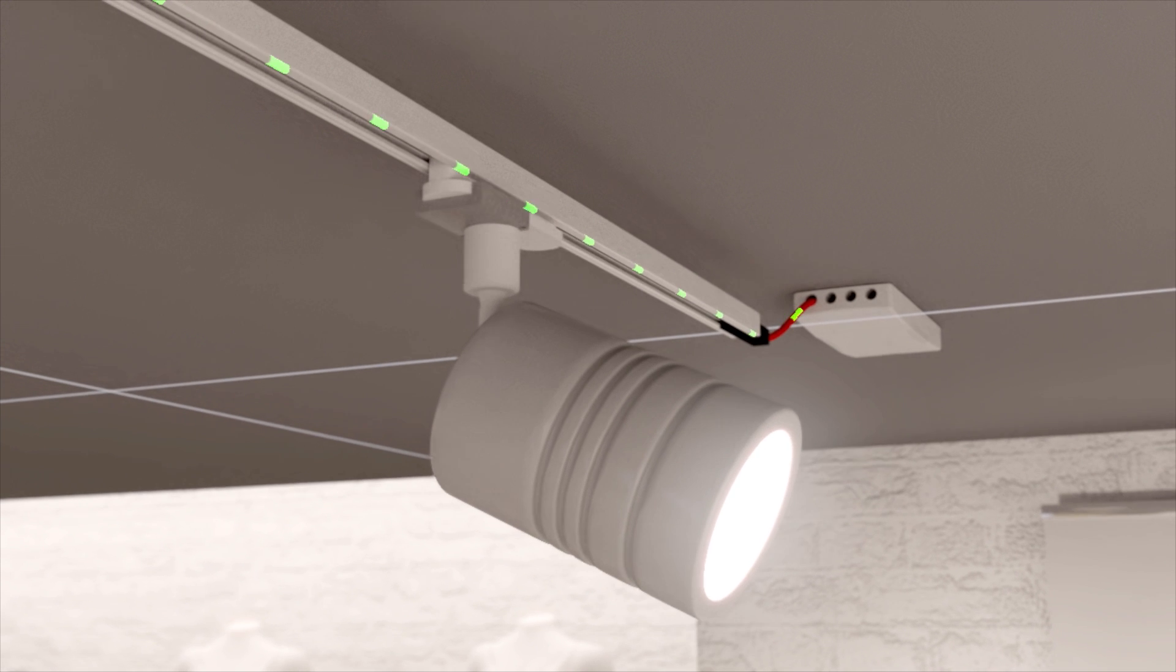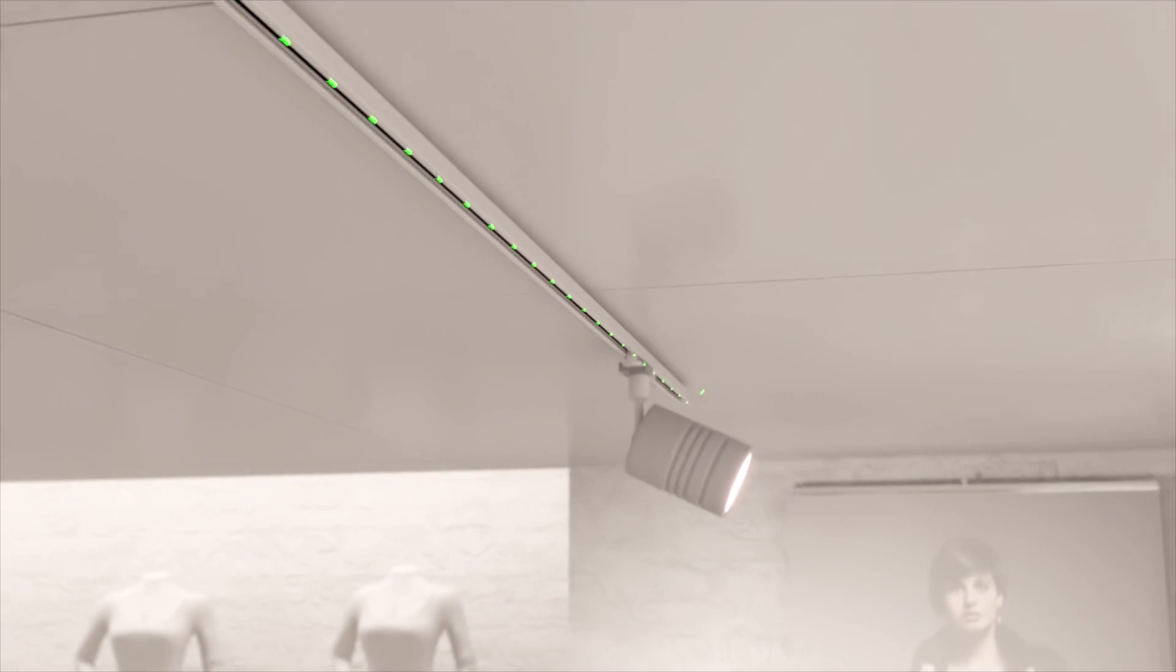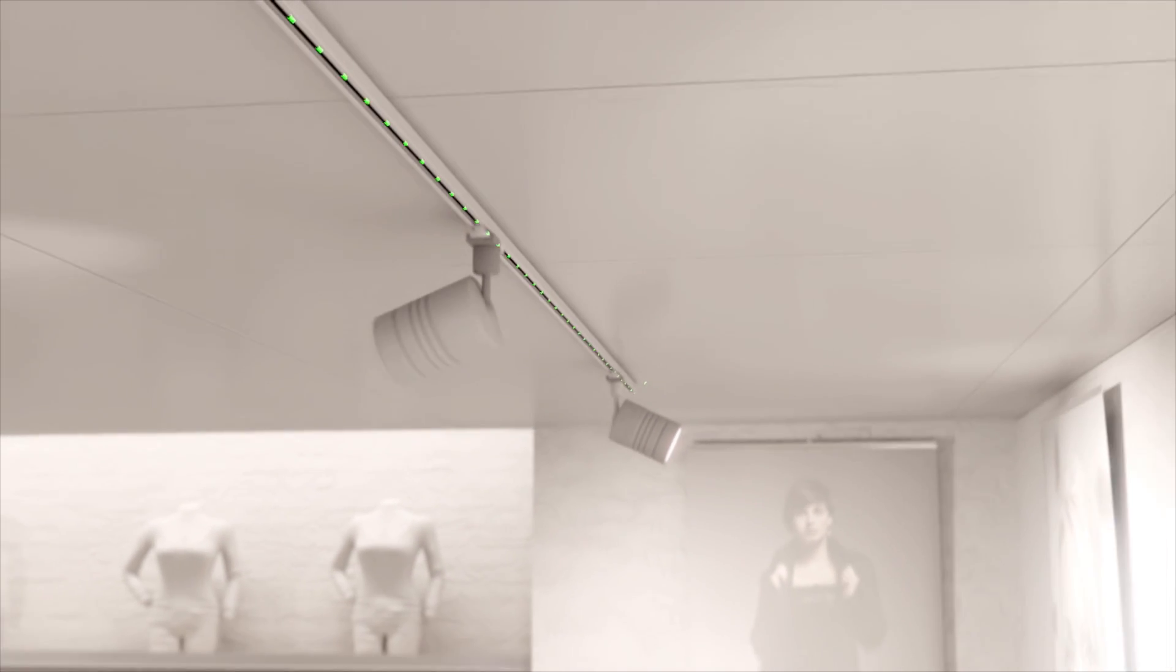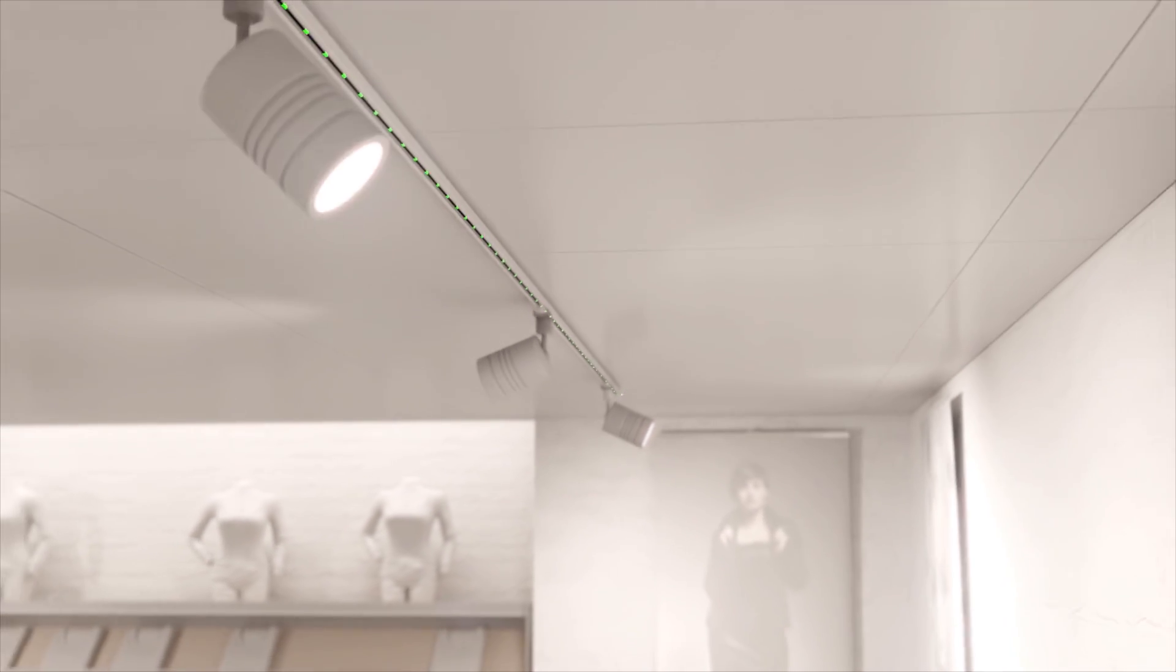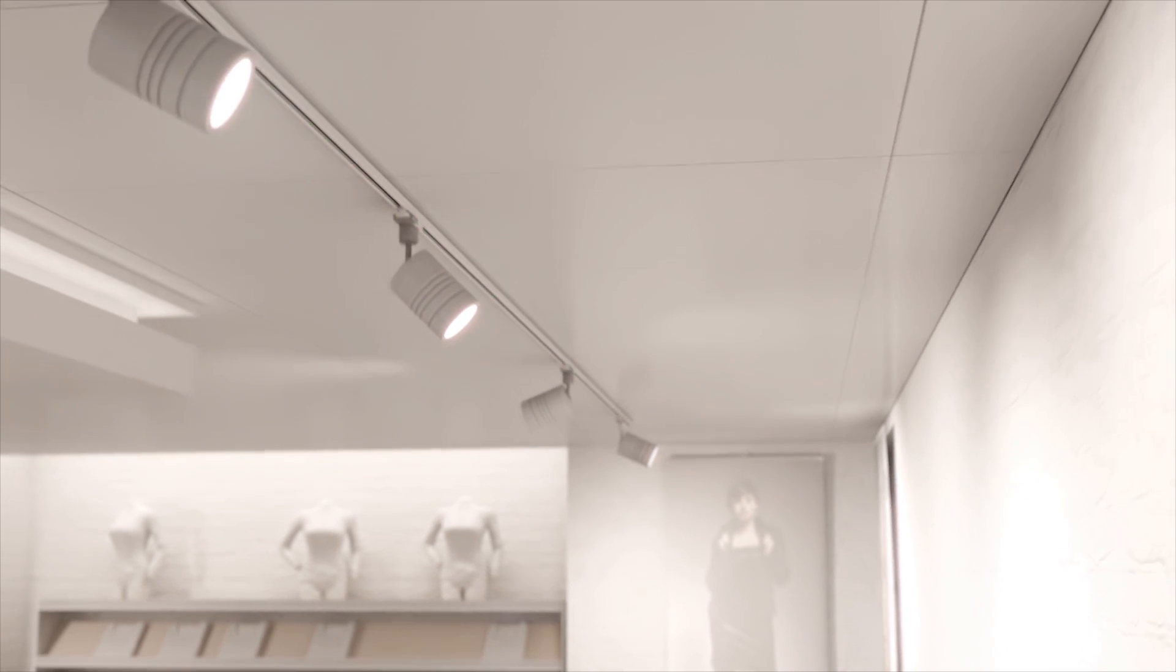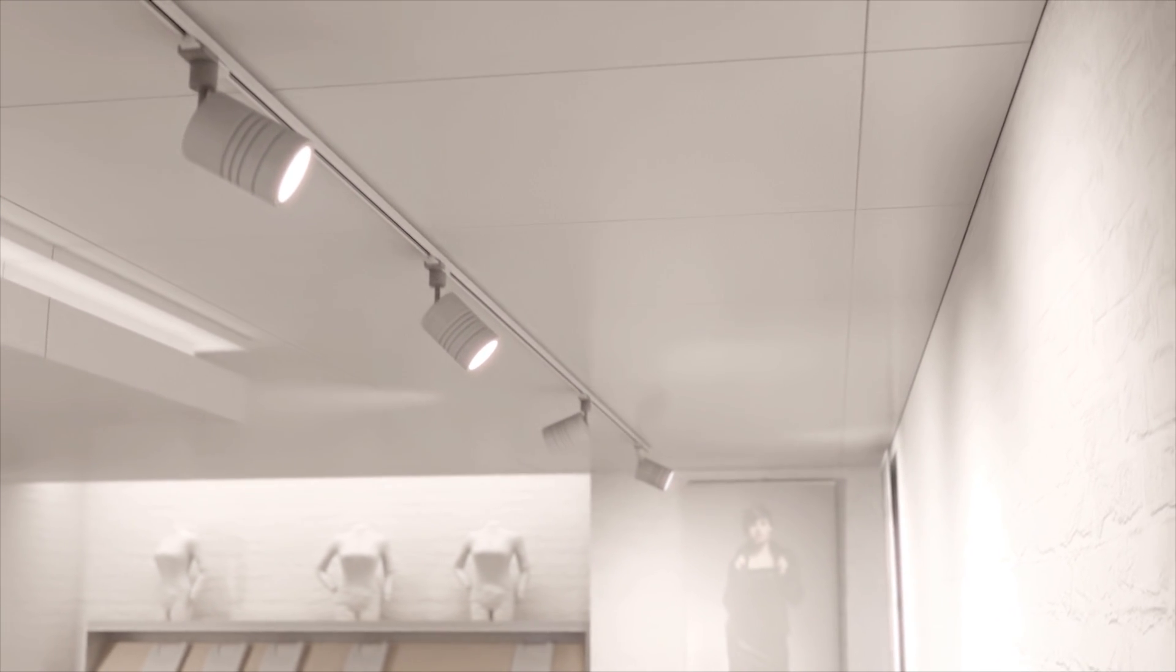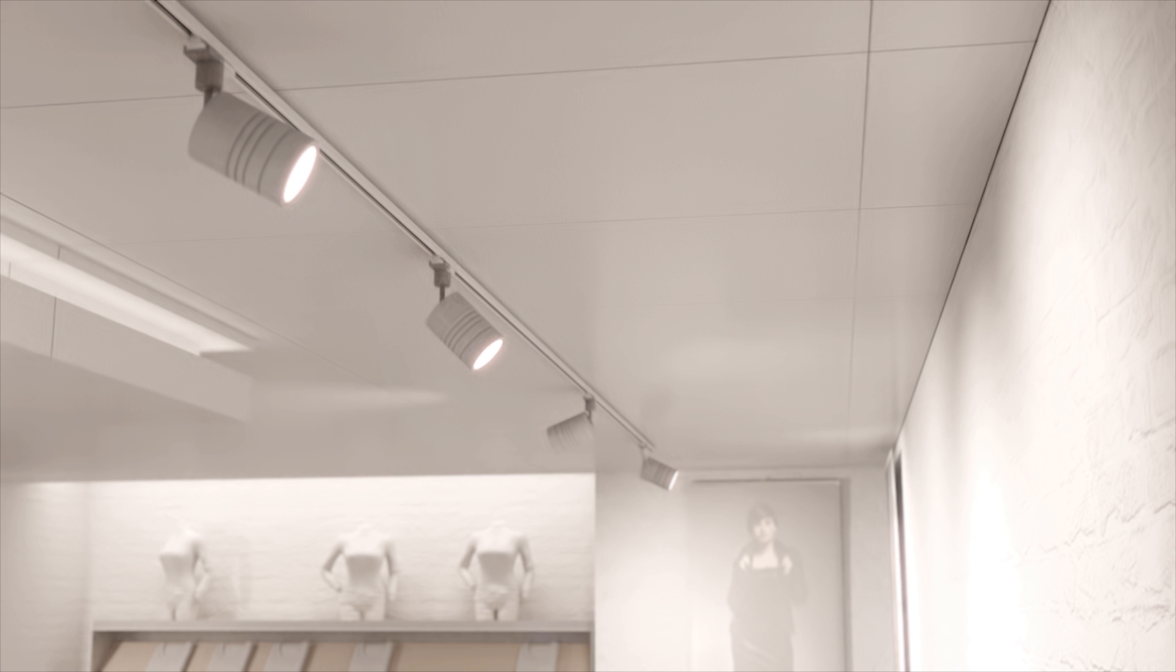The LED driver sends DALI commands via DC powerline communication. Each light point can be addressed and dimmed individually.